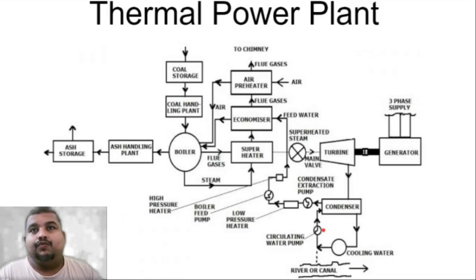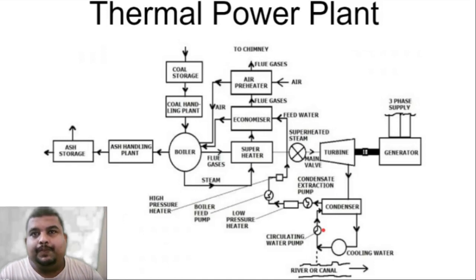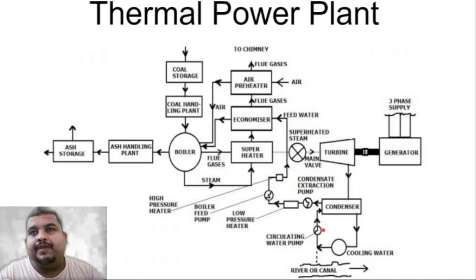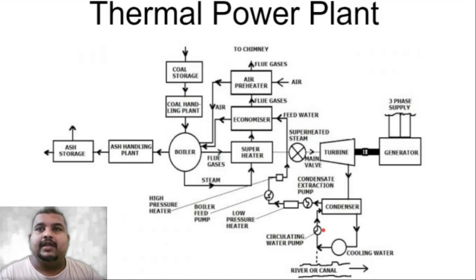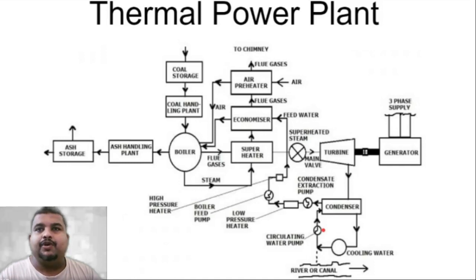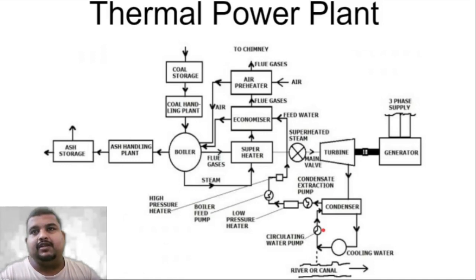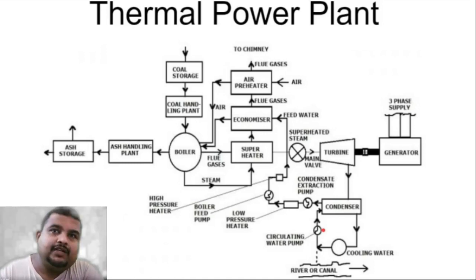The superheater uses the flue gases from the coal burning to superheat the steam. The heat source — the coal burning and smoke — provides heat which is extracted by the superheater. The superheated steam then goes to the turbine, which is at high pressure. After the turbine, we get low pressure steam, and the cycle continues: condensate → cooling water → LP heater → BFP → economizer → boiler → steam → superheater → superheated steam → turbine — this is the complete steam and feed water cycle.